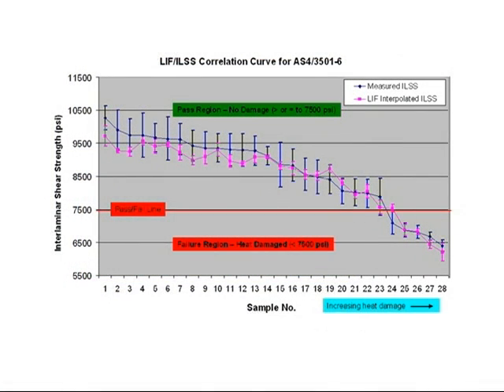Close examination of the LIF emission spectrum allows the instrument to correlate changes in the spectra to mechanical strength properties of the composite. This is achieved by correlating heat damage to changes in the LIF emission spectra for a series of carefully calibrated composite test panels that have been subjected to a wide variety of known elevated temperatures and have known mechanical strength properties.